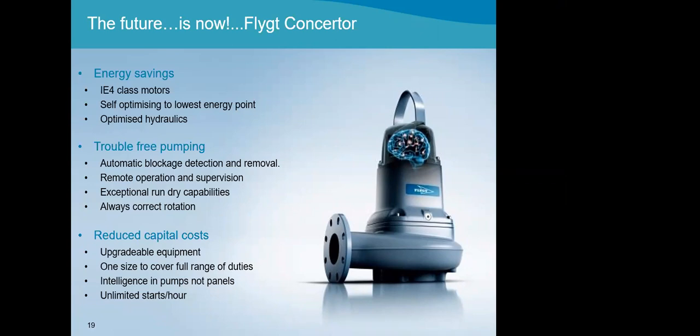This can do various different things. If it senses the impeller is getting rag built around it and slowing down, pulling more amps, it can rotate backwards to take that blockage out. It will do this 20 times to remove the blockage, ultimately passing the blockage, and then you're good to go as you were before. It's a normal pump.